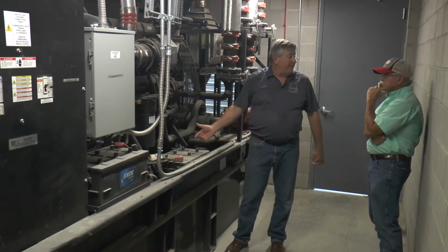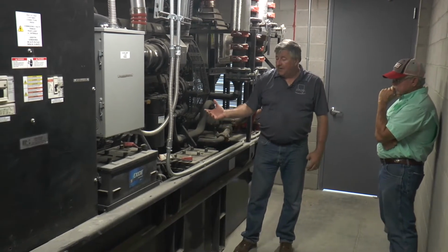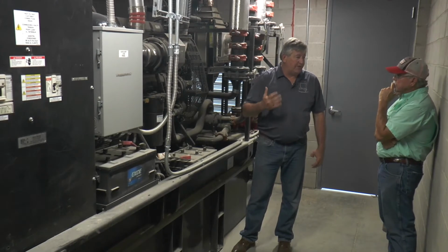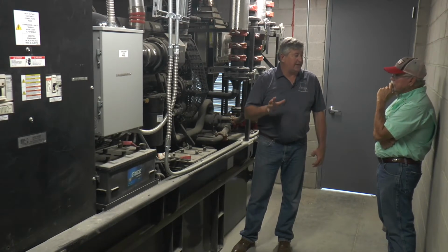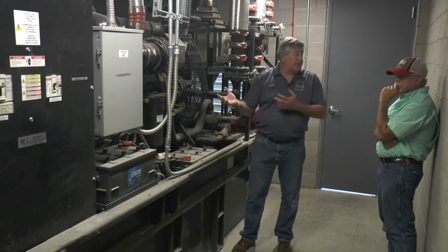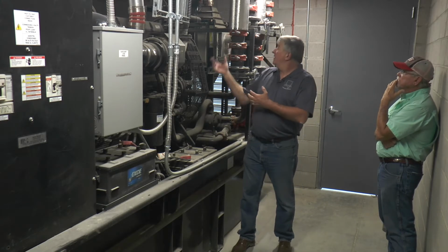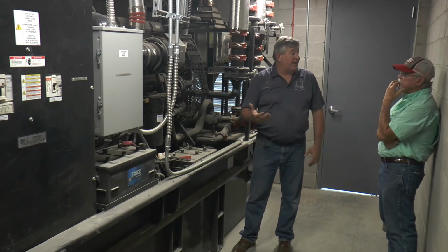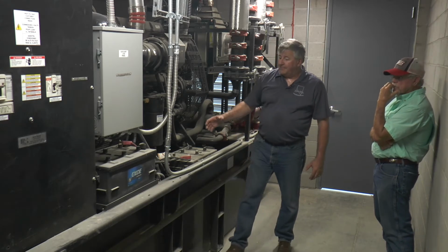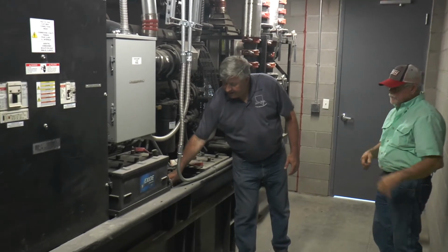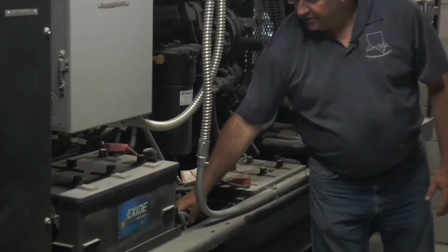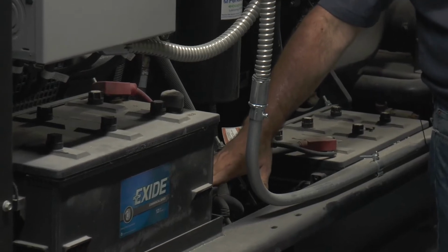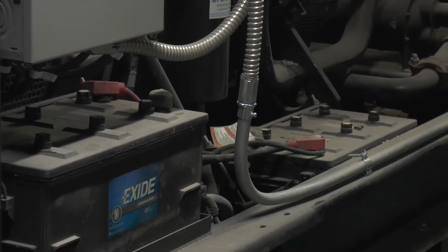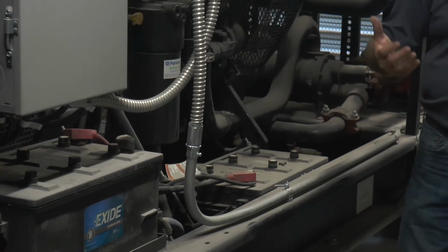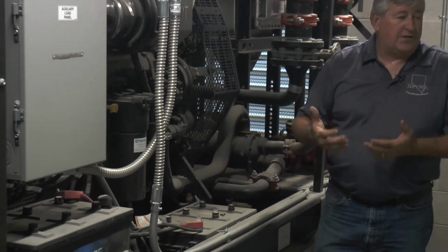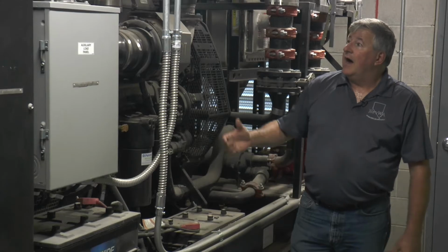Recommend checking the specific gravity of them at least once a year. You'll probably end up changing them every 2 years. They typically will last about that long in our heat. This room is not air conditioned as of yet. They do have a fan, so it might get climatized a little bit. Engine circulation pump right here should be hot to the touch or warm to the touch. Right now, this is thermostatically controlled, keeps the engine between 80 and 100 degrees. So it assures that we have a proper, efficient start when it's called to run.